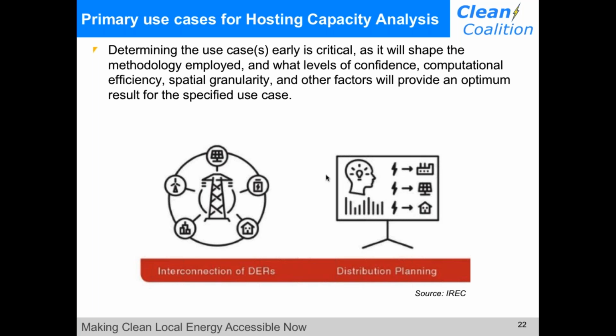On a high level, for the interconnection of DER, the way that's been playing out in leading states is using an iterative method that's a bit more data intensive, which provides more value and accuracy for the hosting capacity analysis results to sync up and be accurate with the interconnection process, and ultimately fulfill and serve that process. For using hosting capacity analysis as a tool for distribution planning, that's more suited towards a streamlined method in which you're running various scenarios over time to see how policy and investment decisions will impact the ability of the grid to reliably accommodate new DER under various scenarios.